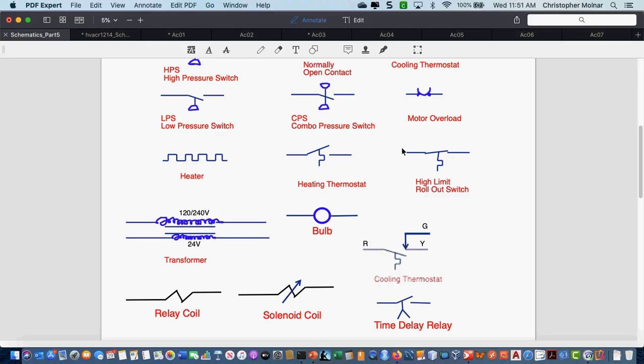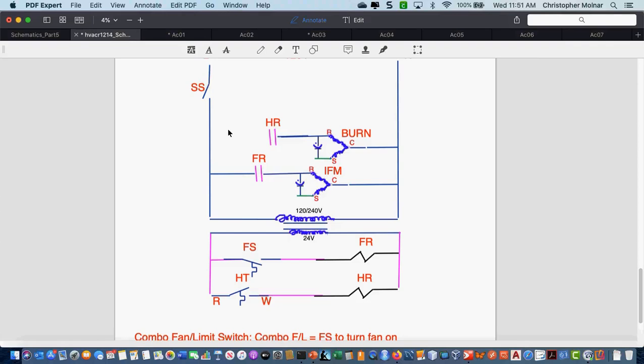Now, a limit switch, is it normally open or is it normally closed? Normally closed. Yeah, because under normal operating conditions, the furnace isn't overheated, and I want that burner to run. So I'm going to take my normally closed switch and put it in over here. We hope it goes in over there. And I'm going to label that HLS for high limit switch.